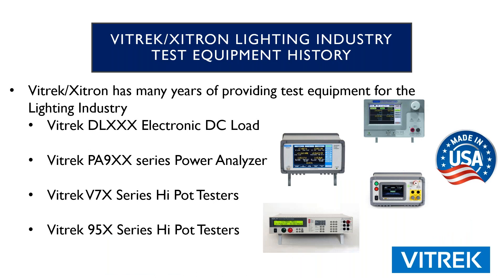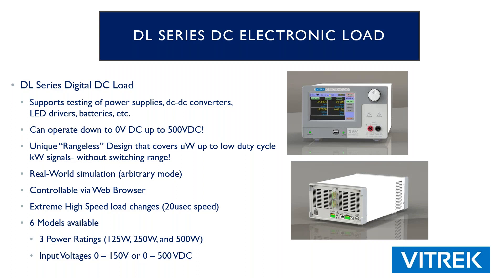On the Vitrek side of things, to do a lot of this testing, you could use our new electronic DC load, certainly the PA900 series power analyzer, and on the Hypot side, our V7X series or our 95X series Hypot testers. The V7X is more on the economy side — maximum test voltage is 5kV. On the 95X, you've got higher test voltage capability plus the ability to measure currents down as low as in the picoamp range.